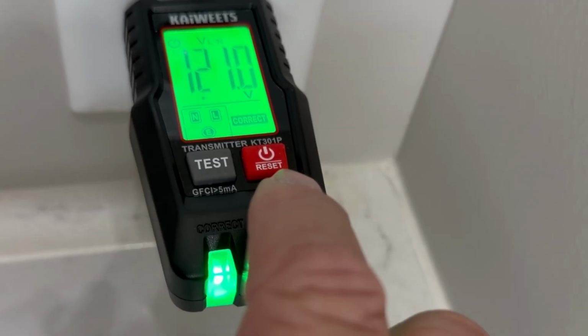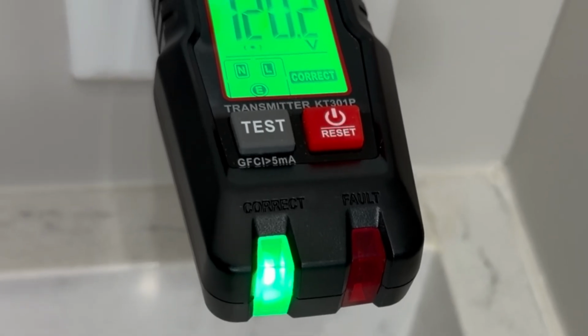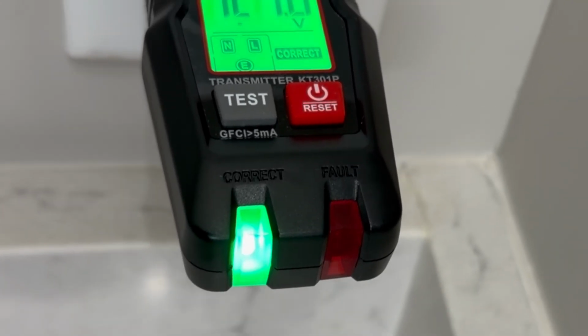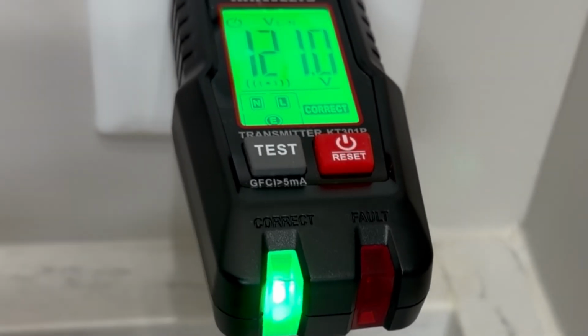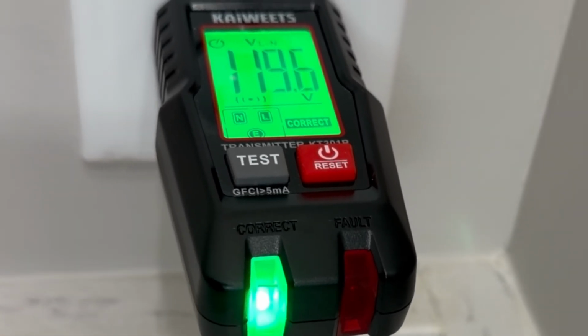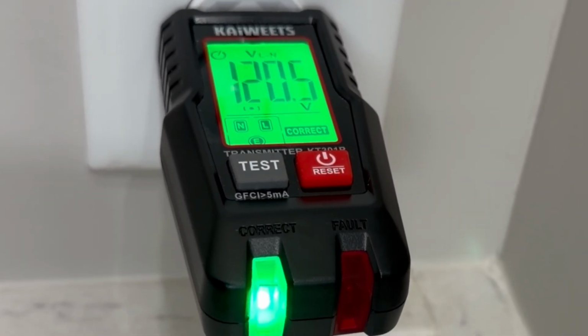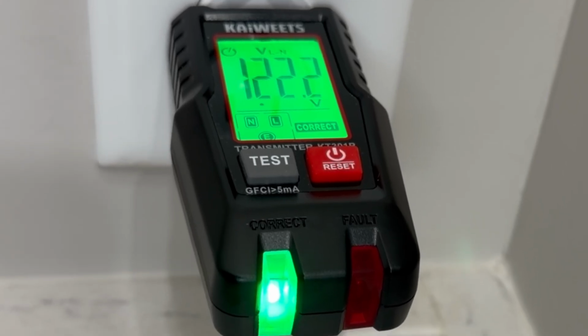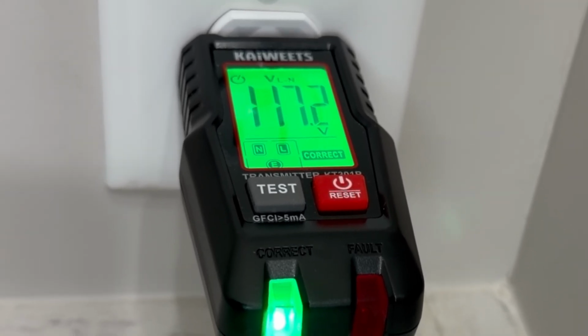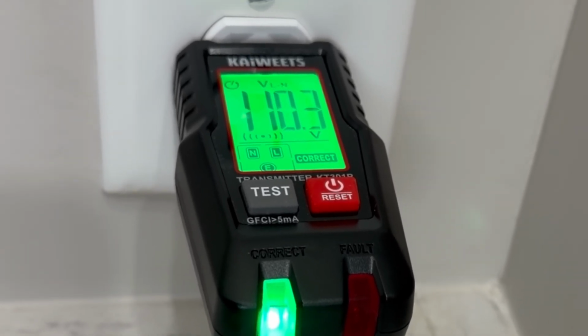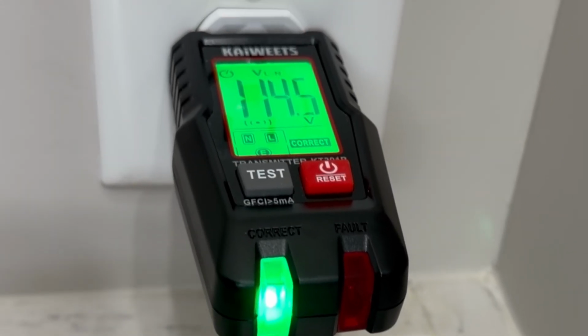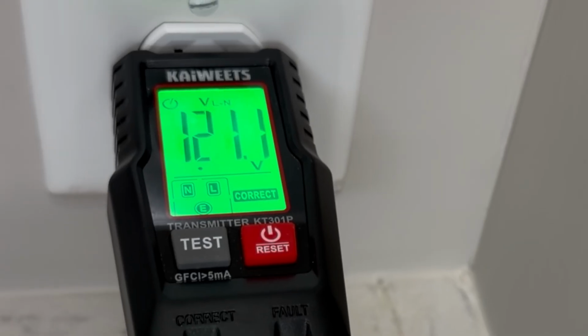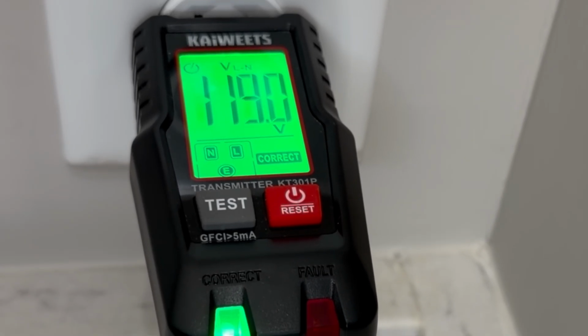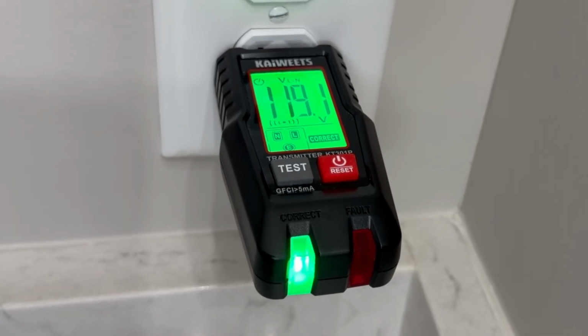It says correct, no errors there on the left side, and the green light solid means there's power flowing through it and all the connections are correct in terms of the ground, polarity, and so forth. Otherwise it would indicate red and state different things in the transmitter. So let's test the ground fault.